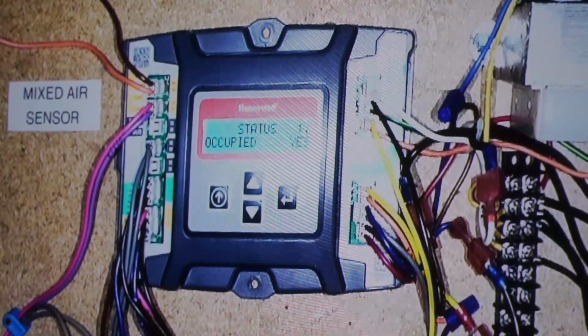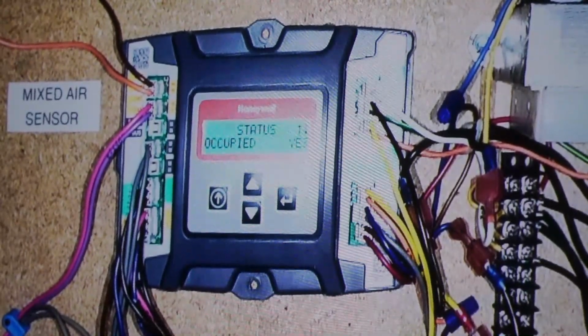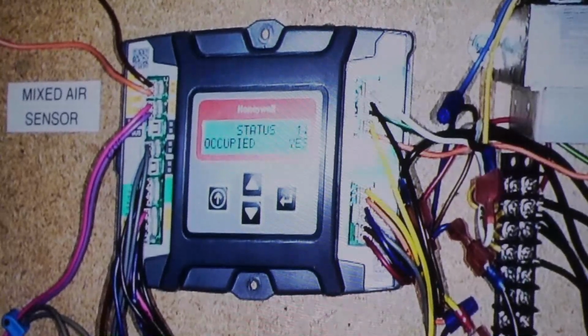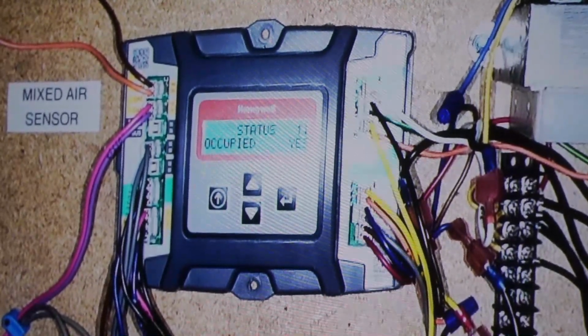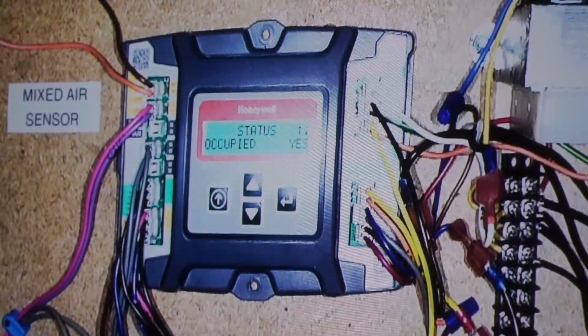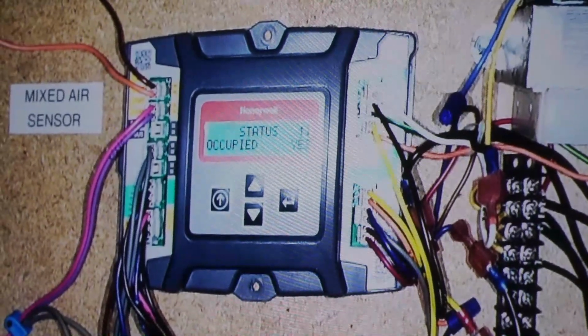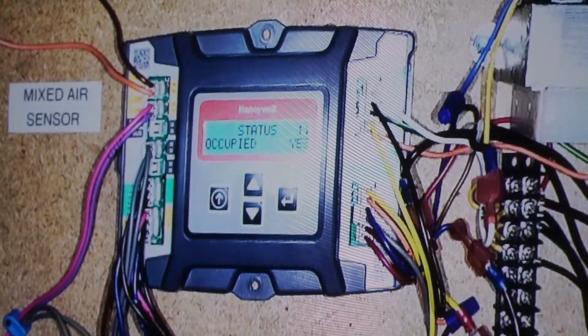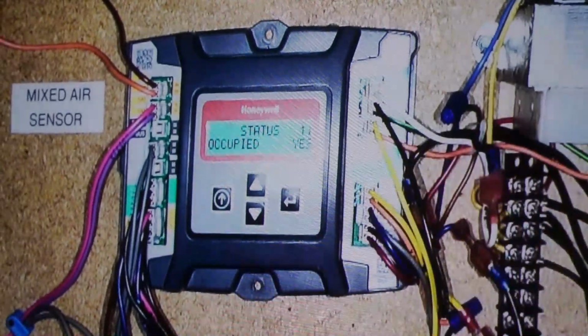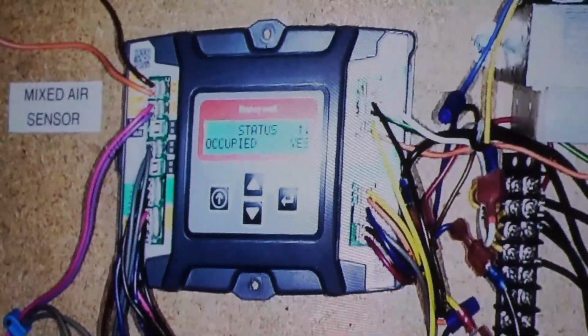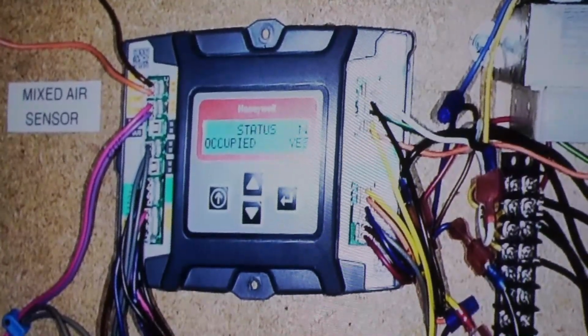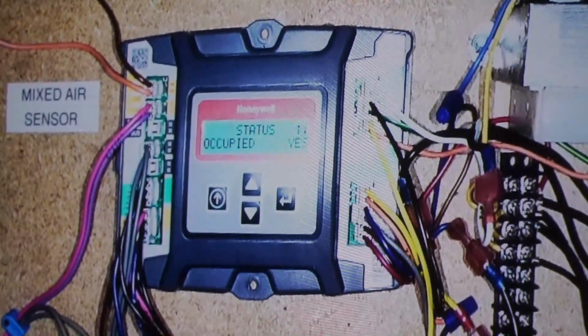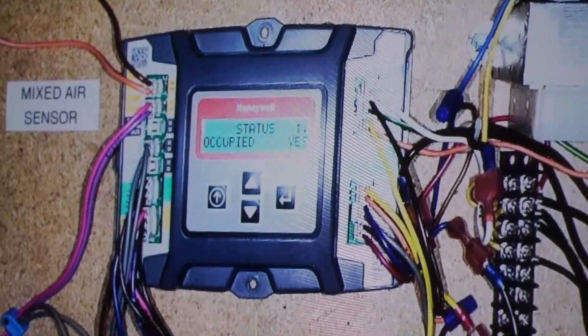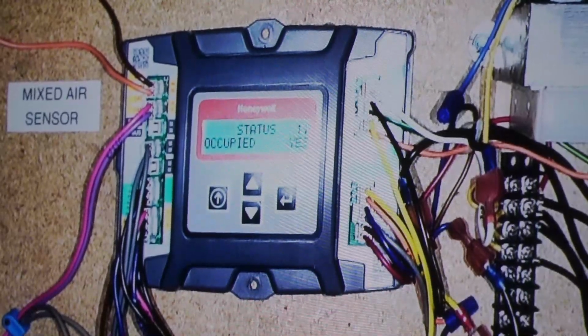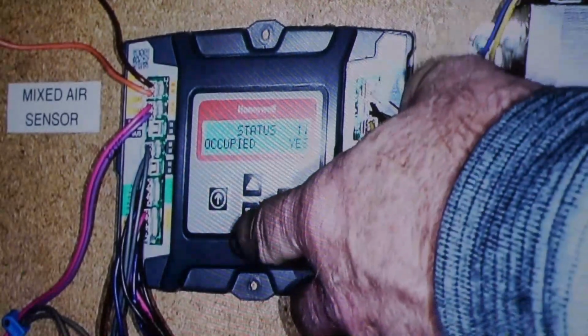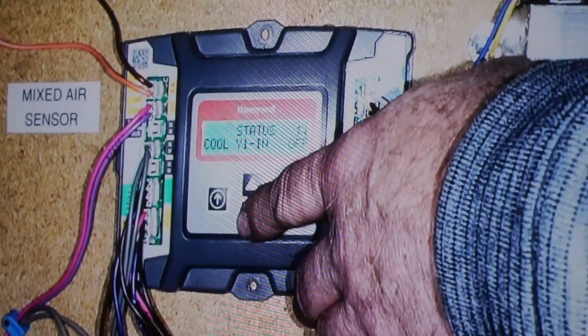Right? Yeah. But the word commissioning gets thrown around a lot in today's HVAC world. Commissioning, this is part of commissioning. Do we have the right sequence? Are we occupied and unoccupied? What are we doing with our dampers? It's gone from very little awareness 10 years ago to we're scratching the surface pretty good and we're getting there. So essentially if we're pulling in 25% fresh air all the time into a space that's unoccupied, how much more is that going to cost us to heat that period when there's nobody there? Right. Energy waste. Right. So therefore, you can save them money by just doing a couple things. Yeah, that's a good call.